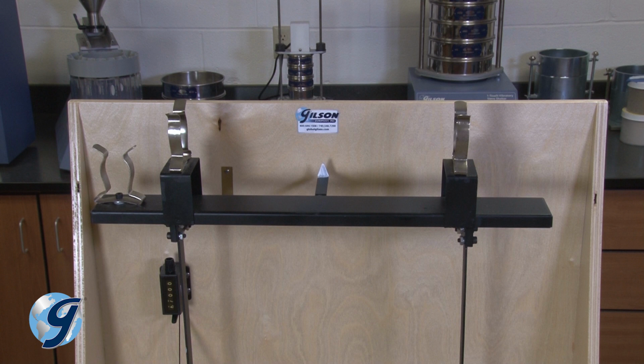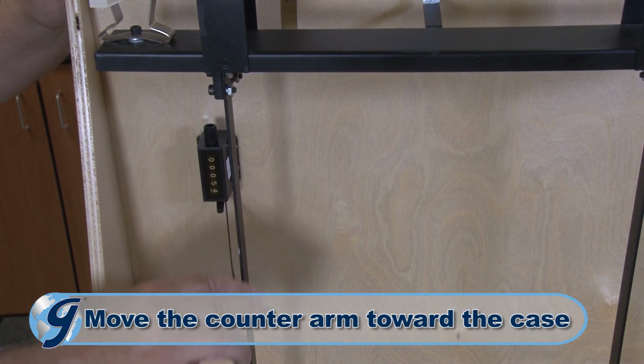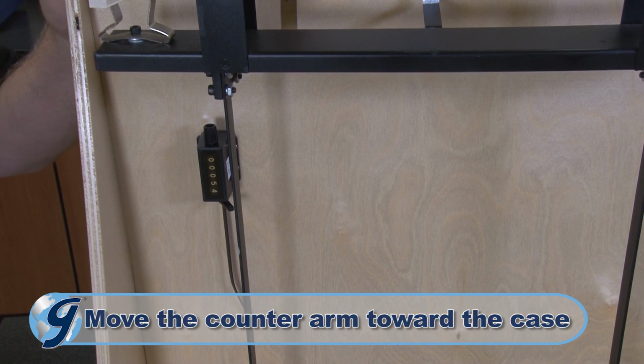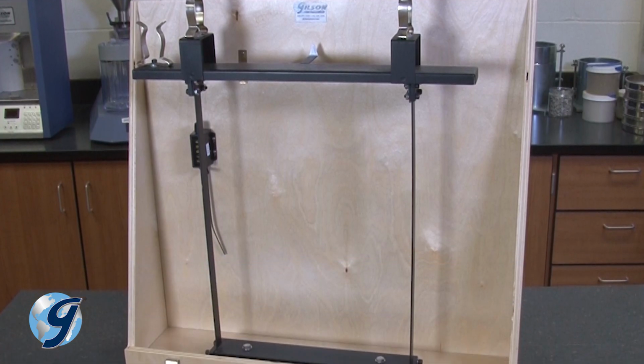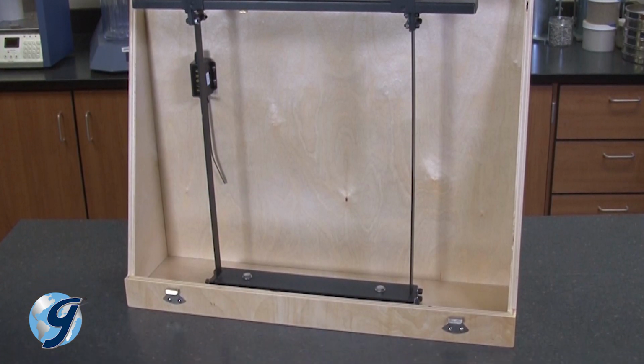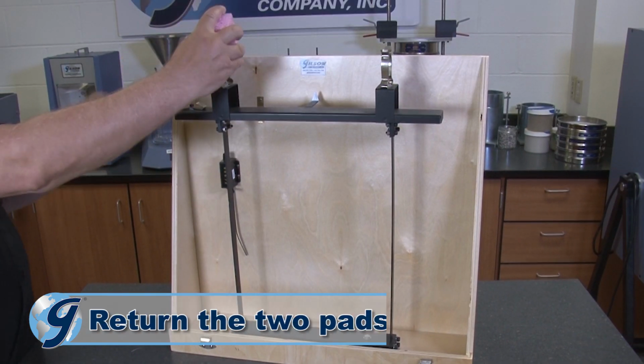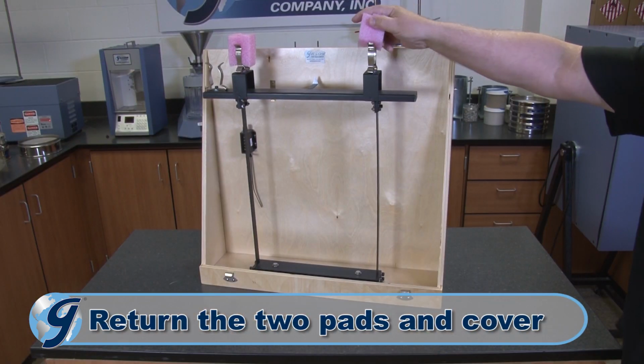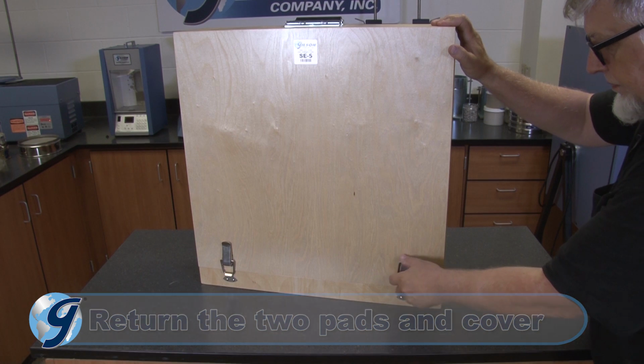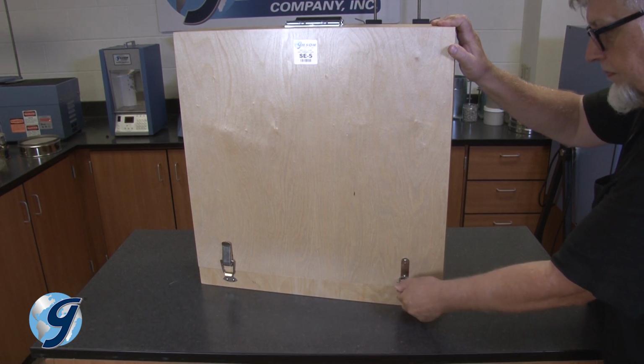To close the Economy Sand Equivalent Shaker, move the counterarm away from the steel strap and towards the case. This will allow the front cover to safely return to the unit. Next, return the 2 pads to the cylinder clips and return the cover to the unit, securing it with the 4 latches.